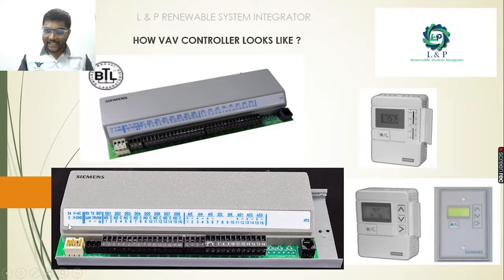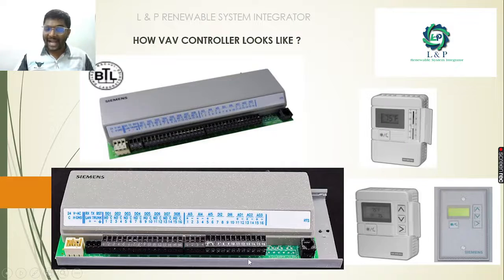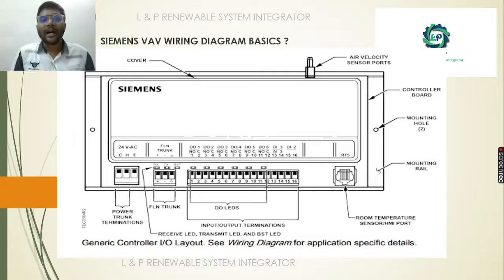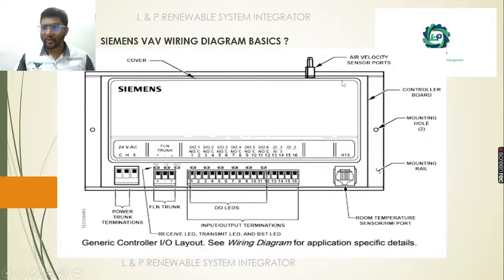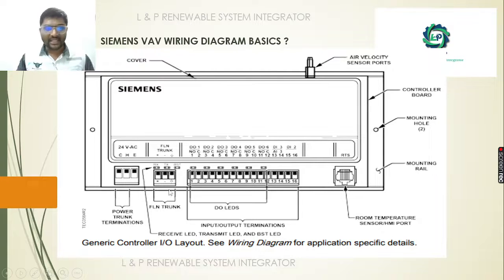This is how the VAV application specific terminal box controller looks. It has power supply terminals, communication terminals, digital output terminals to command outputs, and analog input, analog output, and digital input terminals for monitoring. The RTS port is where we connect the room temperature sensor. This is the basic wiring diagram of this VAV. For the air velocity tubes we have air velocity ports, mounting holes and mounting rails for fixing in the control panel, RTS for the room temperature sensor, floor level network for communication, 24V AC for power wiring, and a terminal block for all inputs and outputs.